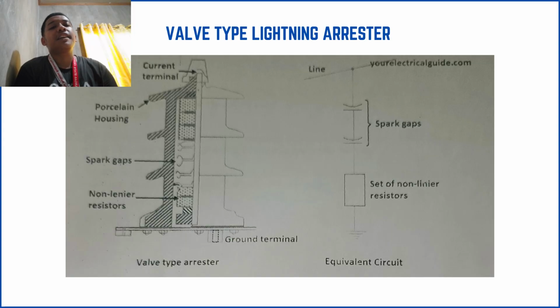Now let's move on to the next slide, which shows the construction and equivalent circuit of a valve-type lightning arrestor. As you can see in the diagram on the left, the arrestor consists of three main parts. A porcelain housing, which provides insulation and protection for the internal components, a series of spark gaps, and a set of non-linear resistors. At the top, we have the line terminal, which connects to the line, and at the bottom is the ground terminal. The spark gaps act as a switch.